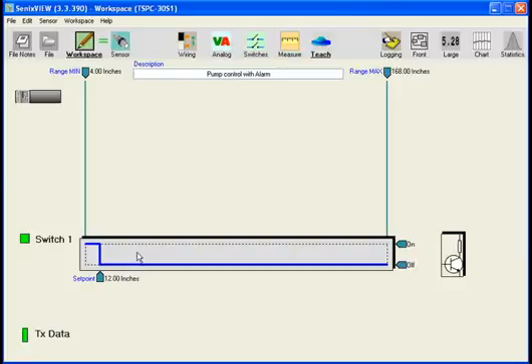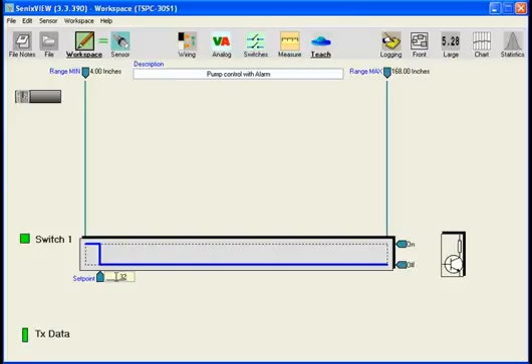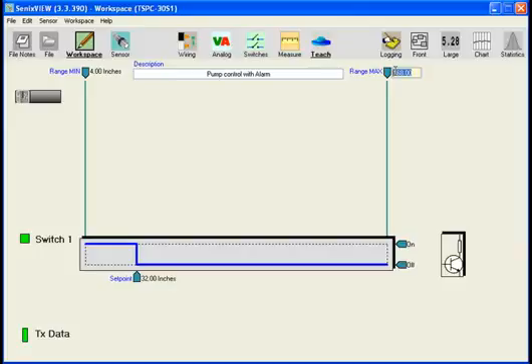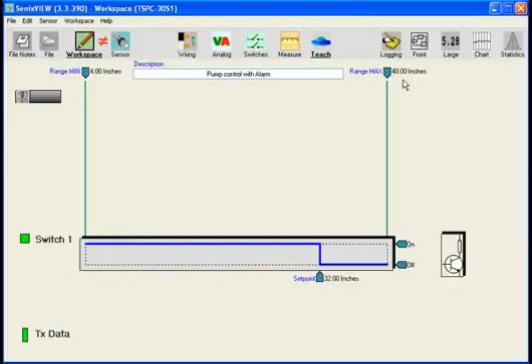We need to make several changes here. The first one is we're going to assume a 20-inch control range for this particular tank and pump. We're going to change our set point from 12 inches to 32. Just to make this look a little easier or clearer, let's change the max range to 40 inches. Let's assume that our tank doesn't allow us to go further than that.